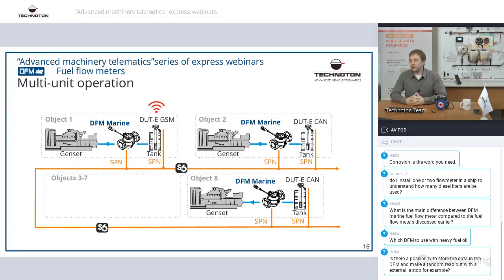Here's another interesting example of using DFM Marine on a diesel generator farm. You can see a very interesting scenario. We have 3 diesel generators. The client wants to monitor the fuel consumption of each diesel generator, and at the same time he wants to know the fuel level in the tank. So here we built an S6 cabling system, and each device got a unique network address. DFM Marine, one address, another DFM Marine, another address, another DFM Marine, another address. Same with DUT CAN: DUT CAN 1, 101, DUT CAN 2, 102, etc.